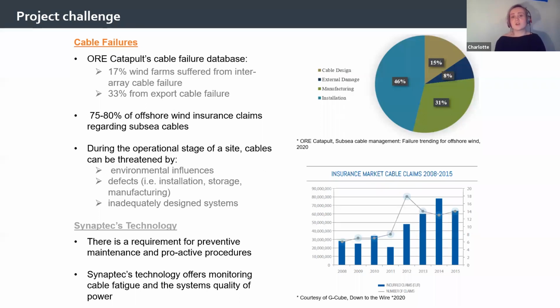Repairs are expensive, and insurance claims are only just the tip of the iceberg of how much subsea cables are affected from various faults. Many faults are because of the harsh environments these cables are installed in, and others are due to the length of time these cable designs and materials can withstand the environments in which the cables are operating. As technology adapts and offshore wind develops, subsea cables are also required to acclimatise and become more reliable. Cable monitoring systems are used to proactively determine when the system needs attention for replacement or repairs through preventive maintenance, or through integration with the control system. Another way to use condition monitoring is when the cable has already been damaged and the event is under investigation. But by utilising cable monitoring technology in proactive ways, certain faults can be avoided. This being said, there are a variety of ways in which the cable can endure faults and therefore eventually lead to failure.